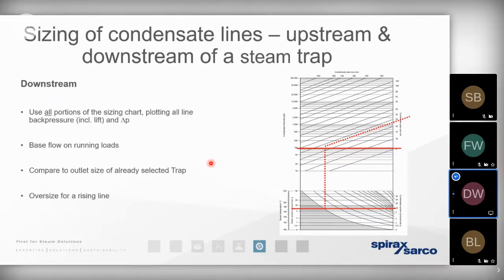So in order to allow for that expansion, we need to treat condensate as a biphase. So we need to consider the fall in pressure. That's going to tell us the amount of expansion that we need to contend with in the flash steam, and the mass flow rate of the condensate arriving at the trap. That's going to give us the information with regards to how we size the condensate pipework correctly, considering that condensate that has undergone a pressure drop needs to be considered a biphase. Again, the good news is you can refer to that useful calculator or configurator on the app, and that will help you with the sizing.